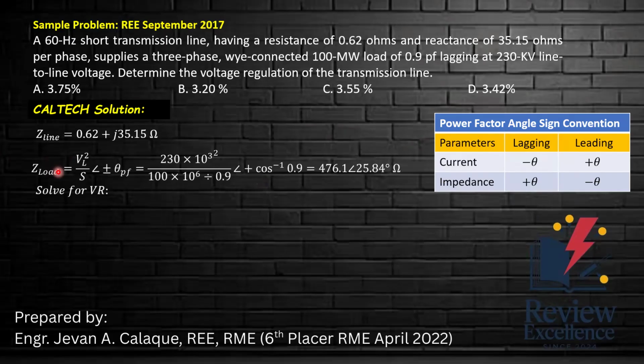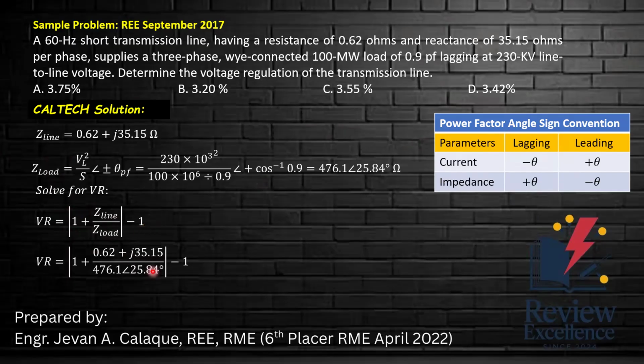The formula for voltage regulation is the absolute value of 1 plus Z line over Z load, minus 1. Let's substitute: absolute value of 1 plus the line impedance, which is 0.62 plus j35.15, all over the load impedance of 476.1 at an angle of 25.84 degrees, and outside the absolute value we subtract 1.